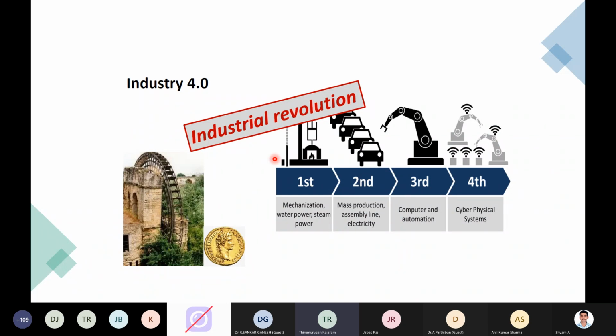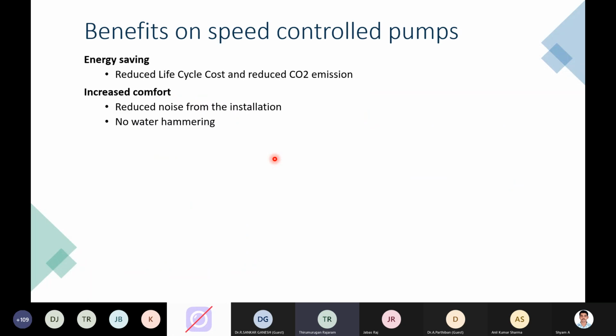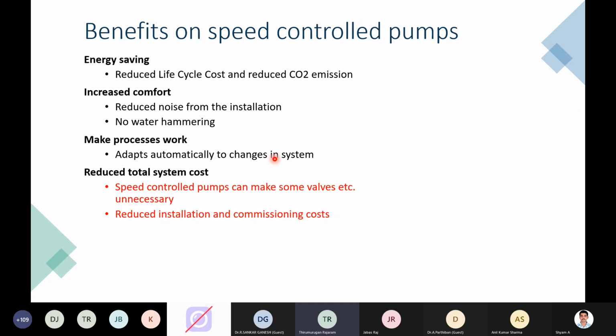So obviously these pumps also can be automated, so more adaptation on understanding the pump performance, reliability, and availability also becomes important here. Speed control helps you reduce your life cycle cost, your CO2 emission, and noise from installations, with no water hammering, and it adapts automatically to changes in the system. That is so important because, as I said, the peak demand is not always there. There are always seasonal changes, and the demand also fluctuates in any industry.